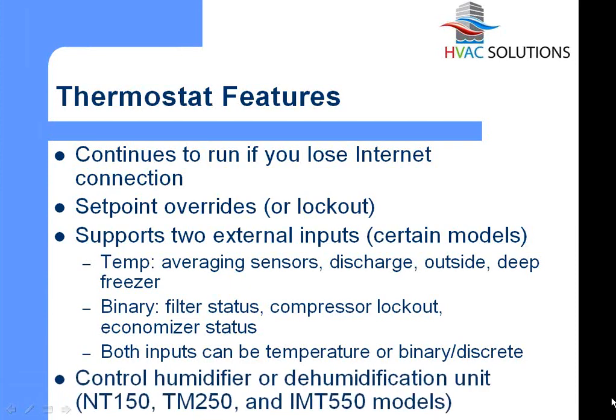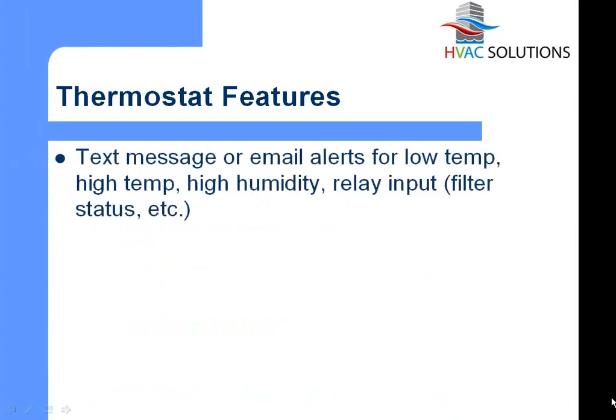And then three of the models, the NT150, the TM250, and the IMT550 models, also have built-in humidity sensors in them, and you can use those to either energize a humidifier, such as in a residential house or in a library or something like that, or you can use it to enable a dehumidification unit or a dehumidification sequence on the rooftop unit, and that would come up in more commercial applications. So that humidity sensor can be used either way. And in the case of the 550, it could actually be used for both scenarios at the same time.